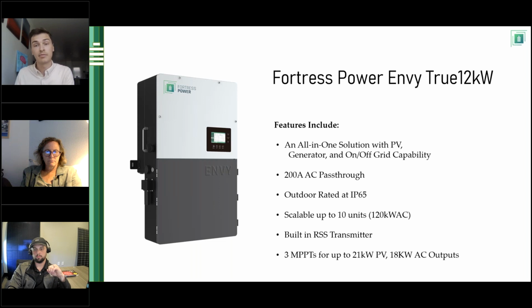But with the advent of 9540A edition 2 coming, we released our newest Envy True12kW. It is a multi-mode string inverter and all-in-one solution, scalable up to 10 units for 120 kW, outdoor rated, with 200 amps of AC pass-through. So you can certainly move closer to what we'll call whole home backup.